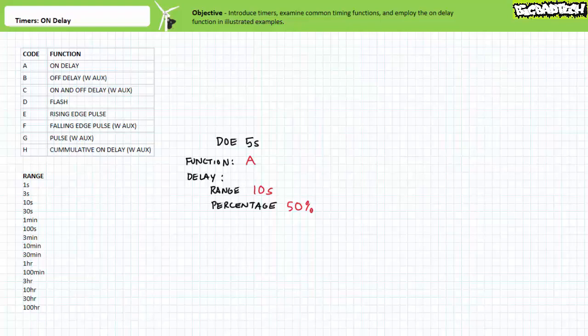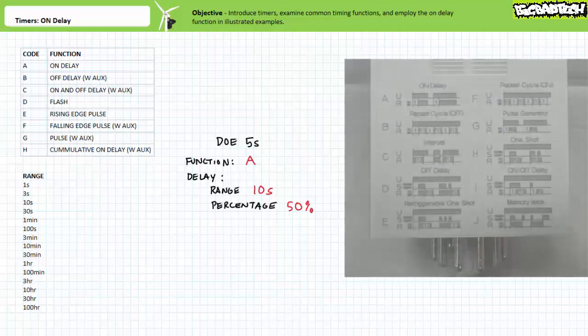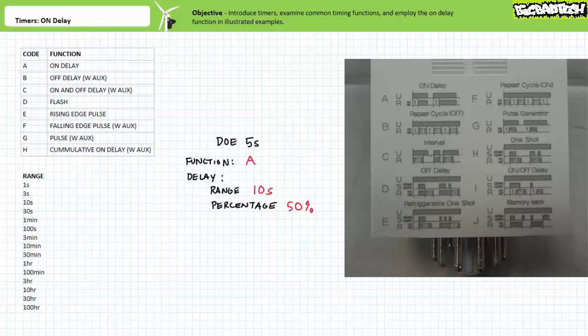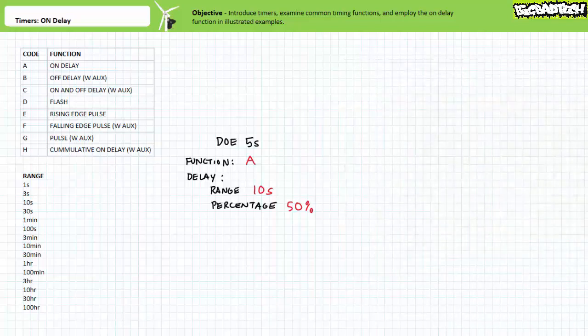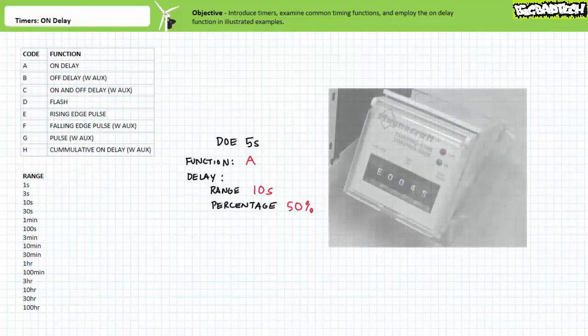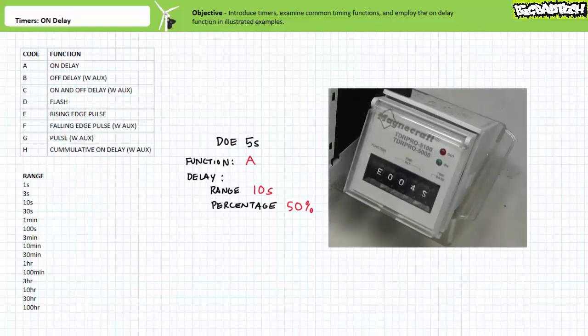Troubleshooters take note: a multi-function timer executing the right function at the wrong time needs to have the delay adjusted. In contrast, a multi-function timer executing the wrong function at the right time needs to have the function adjusted. The misinterpretation of functions is not a rare occurrence, and you need to be aware of this possibility. Note certain manufacturers include a handy cheat sheet on the side of the timer that graphically illustrates the timing diagrams of available functions. If a timer doesn't have this feature, a technician must consult the data sheet. Also note certain manufacturers enclose the adjustable components under a plastic cover.